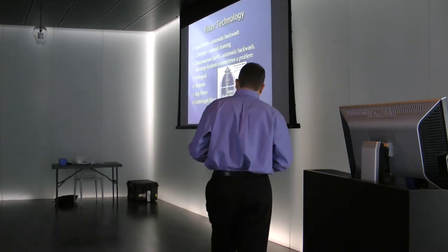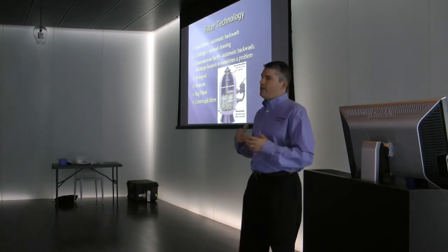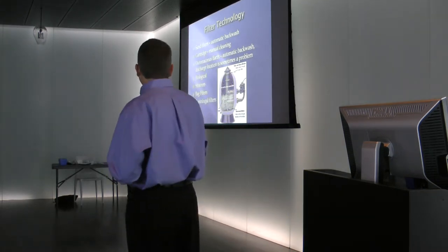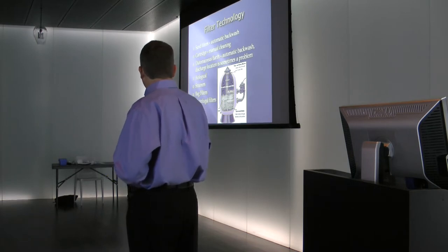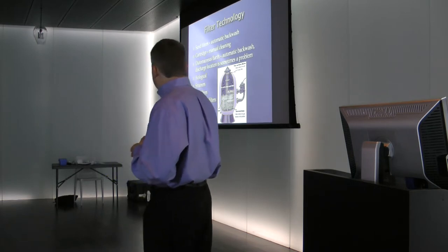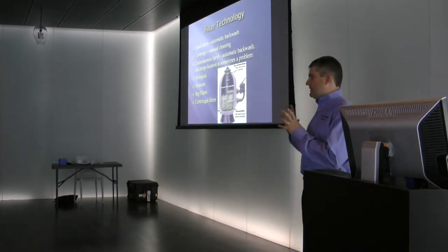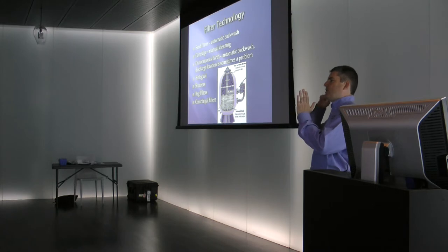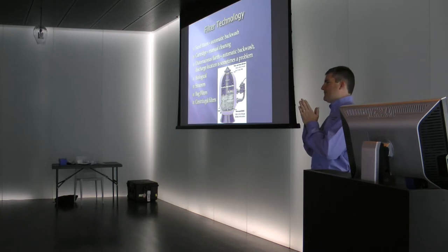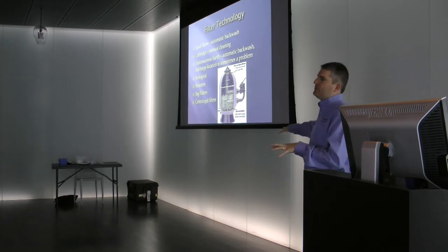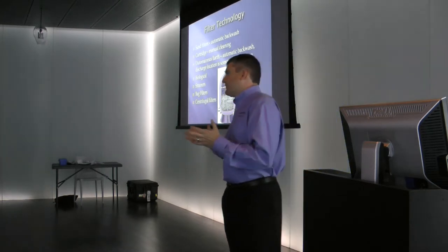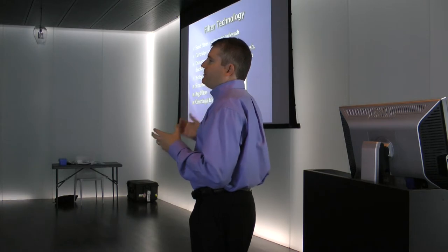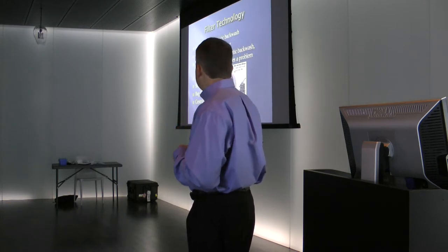Biological filtration is using bead filters. This is what we would use on a koi pond or some kind of fish system. Strainers, we just talked about that. Centrifugal filters: imagine you had a cone and you take water in tangentially into the cone and it's spinning around, the heavier debris is going to fly out to the outside where you can take it out of the system and get rid of it. And the lighter stuff, which is hopefully just the water, comes out of the bottom and moves through the system. We've used that to separate sand from water, even before it gets into the pump, it'll automatically throw away the heavier debris.